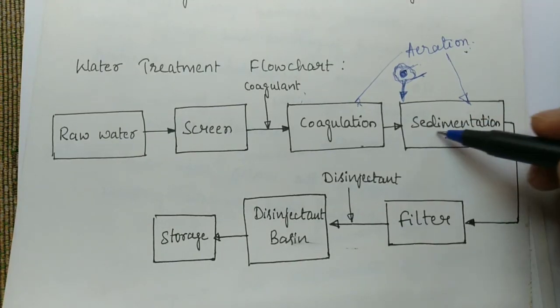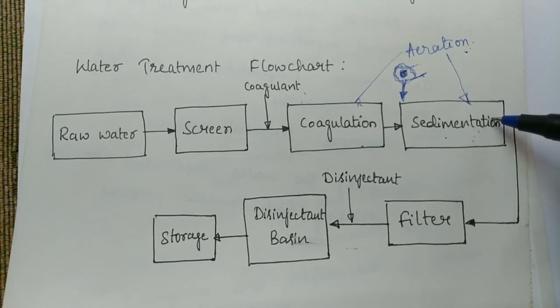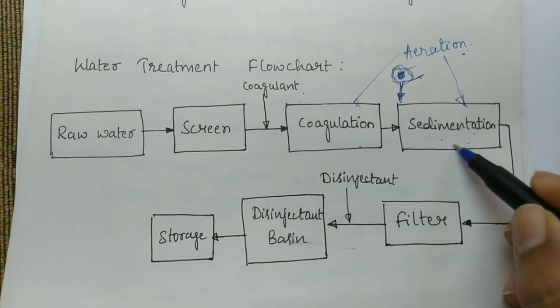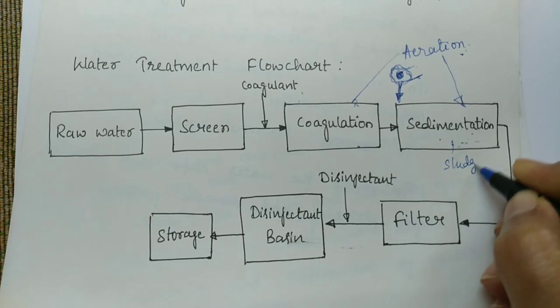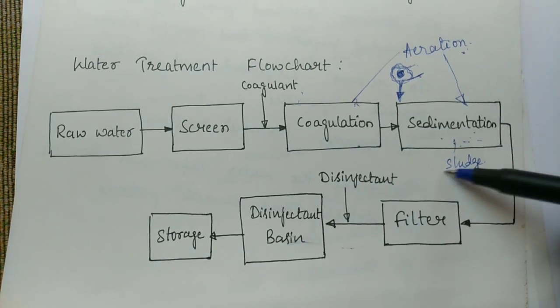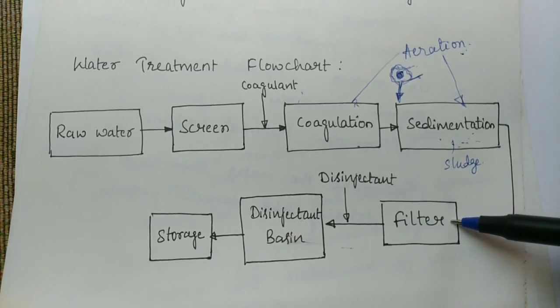Sedimentation, as the name suggests, is a process wherein we remove sediment particles. We give some detention time to the water — we give it rest in a pre-measured tank. With that rest, the water comes to a standstill and particles which are heavier in size, due to attraction by gravity, come to the bottom and get settled. The particles settled at the bottom are called sludge and are periodically removed. Water from the sedimentation tank is then taken to filtration.